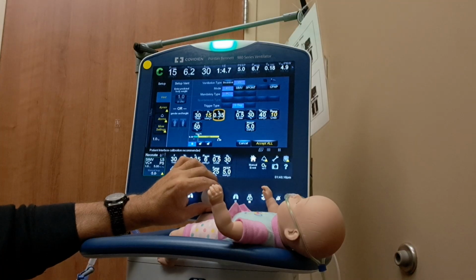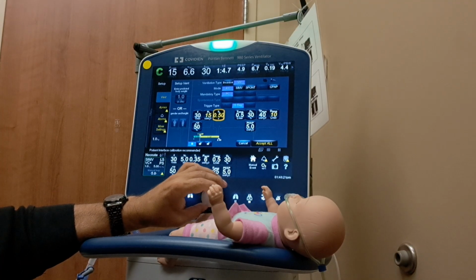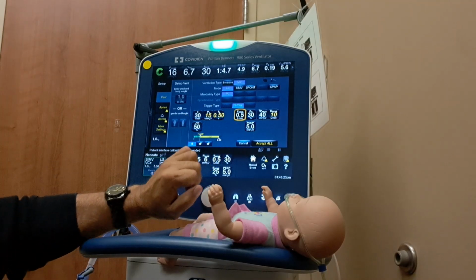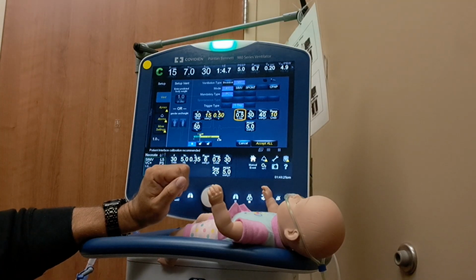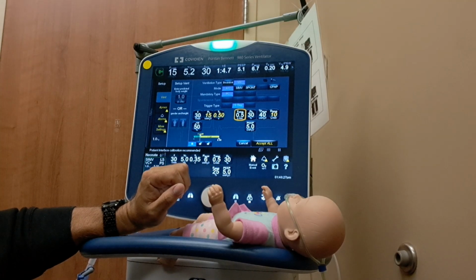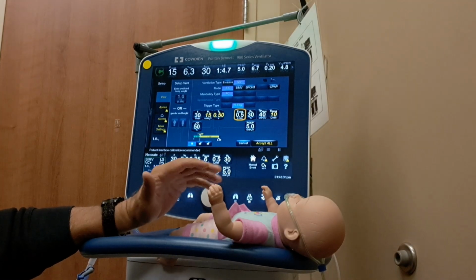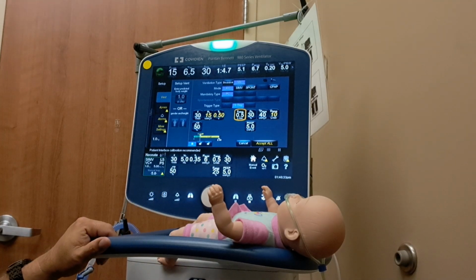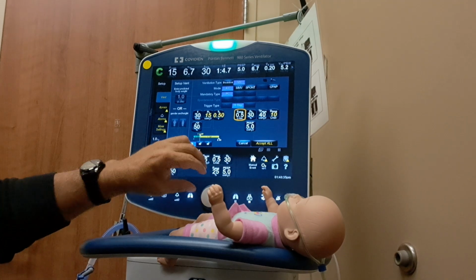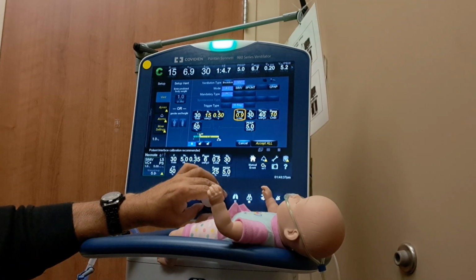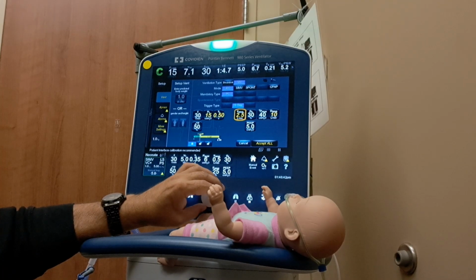I time should always be set at 0.5. Sensitivity, because some interfaces are not occlusive devices, the RAM cannula is an occlusive device, and some occlusive devices develop leaks. So we'll adjust our sensitivity up so that the ventilator will not auto cycle. So we'll go ahead and bump that up to, let's say, 3.